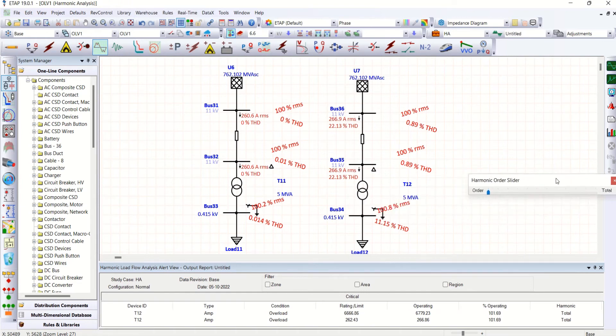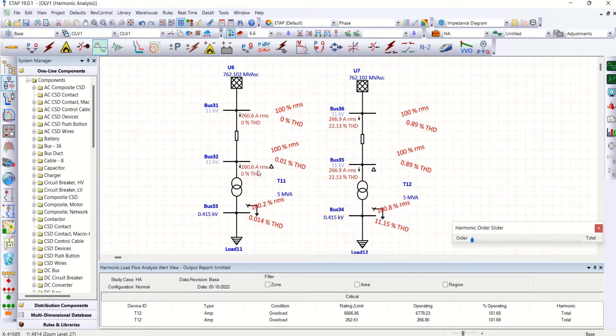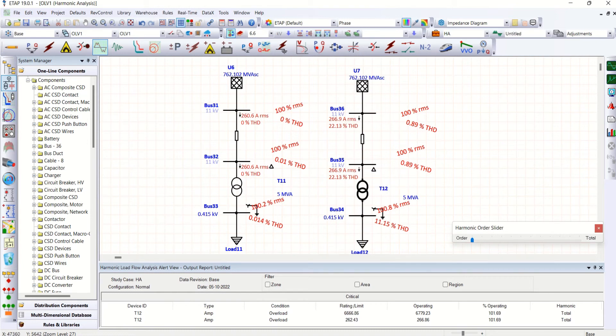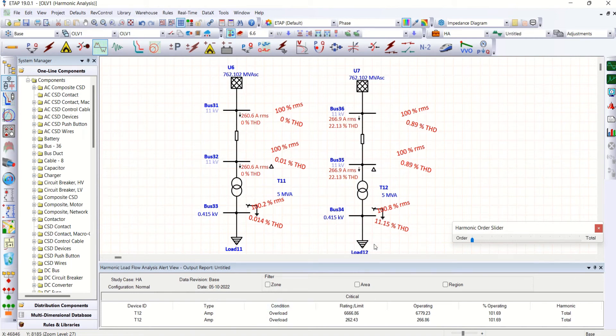Now see the difference here 260.6, whereas one with harmonic load 266.6. Now look at T12. T12 means that this transformer, this transformer is overloaded. Overloaded. Why this is overloaded? Because of presence of harmonics.